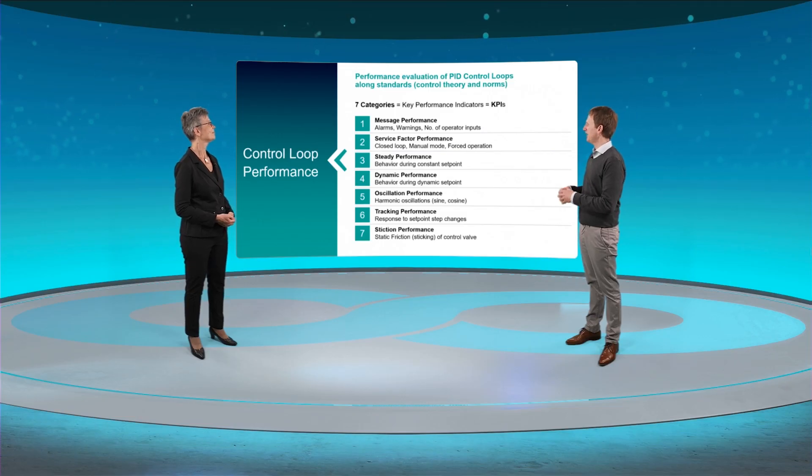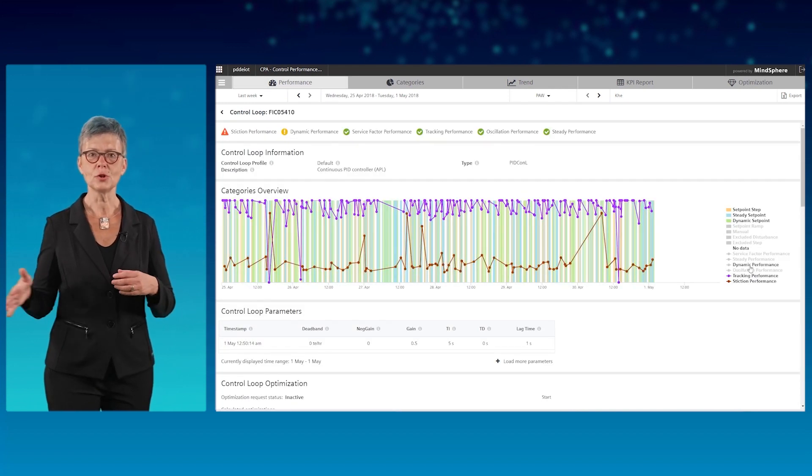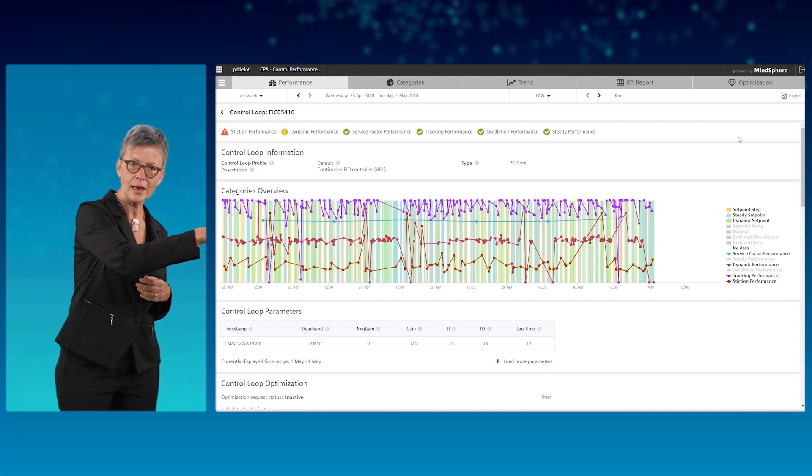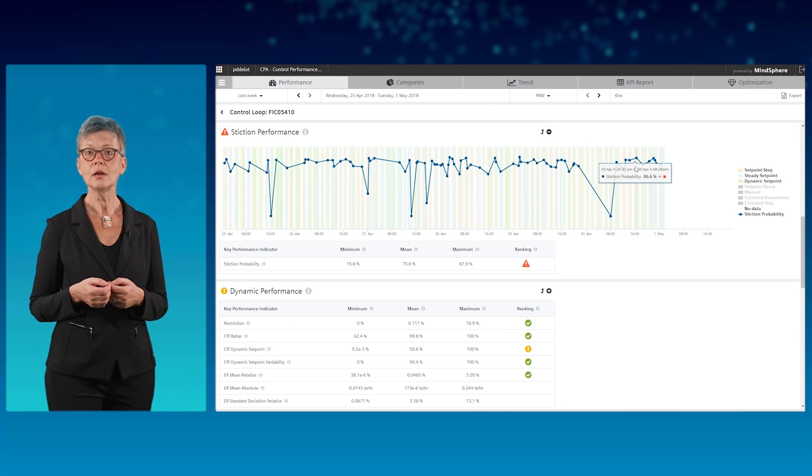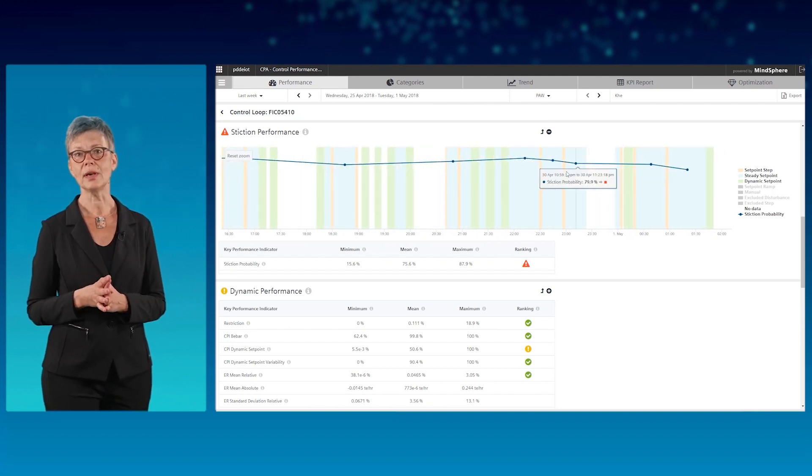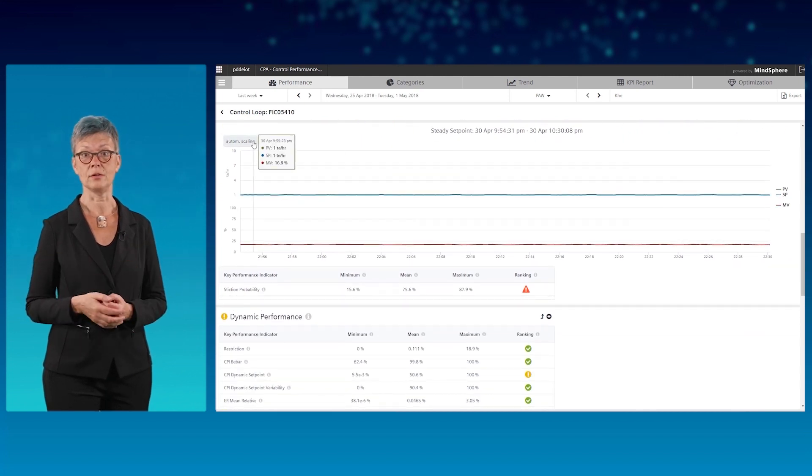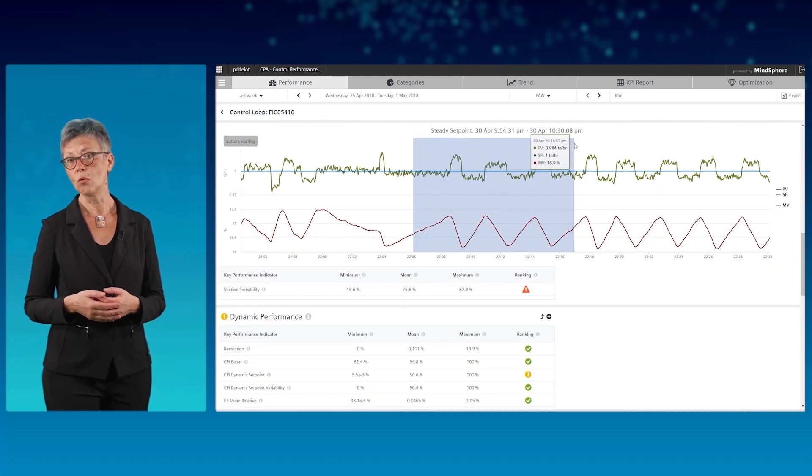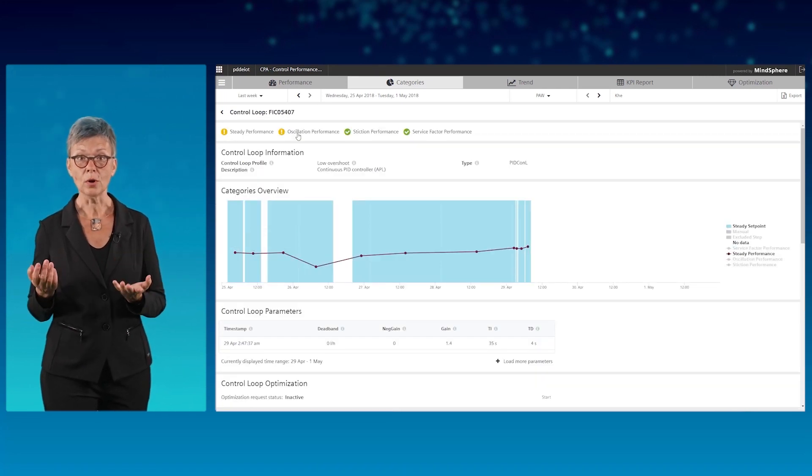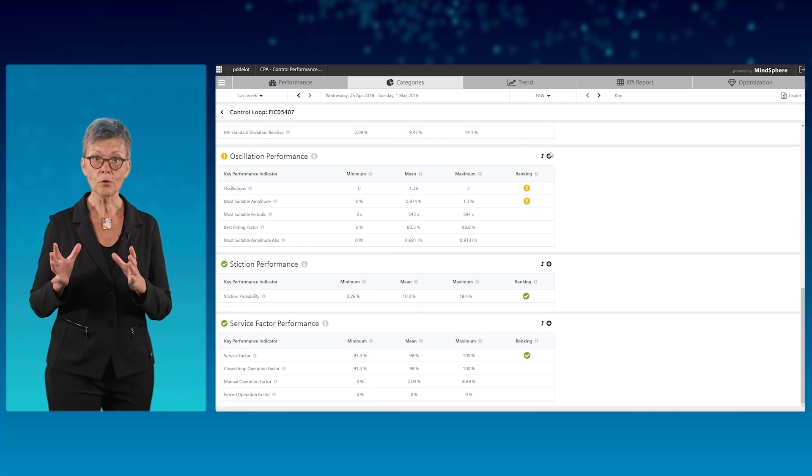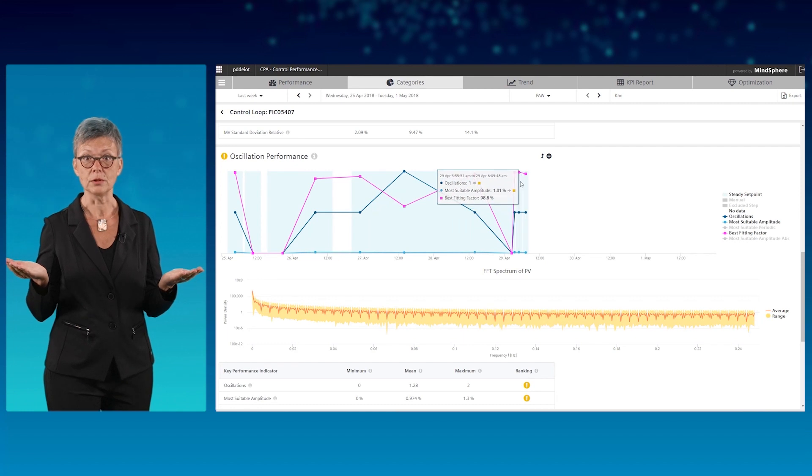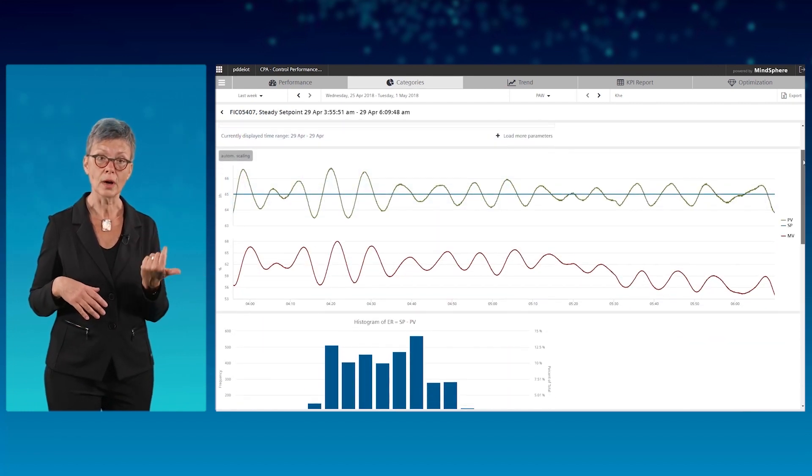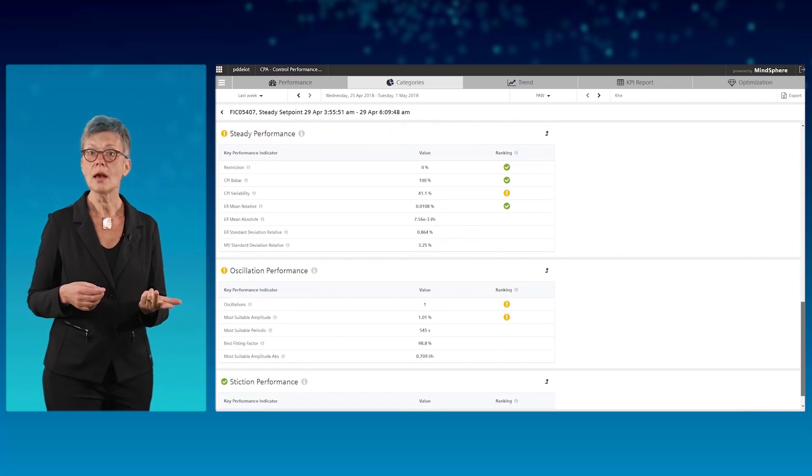Impressive! Can you show me those details? Well, for each loop, you can see how performance has been changing over time for the various KPIs. And you can investigate time series plots. Check out this example where CPA detects a sticking control valve. It's a simple AI that detects the pattern. Or quite common oscillations. Apart from time series plots, you get additional information tailored to each KPI, if needed even for a specific time interval. For example, histograms, scatter plots, average oscillation period, and many others.